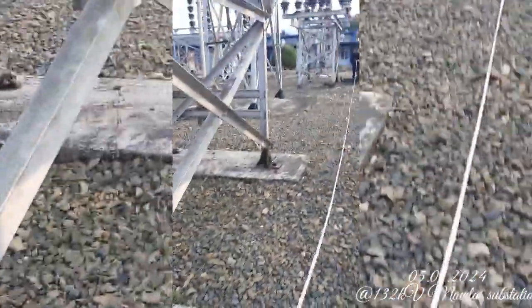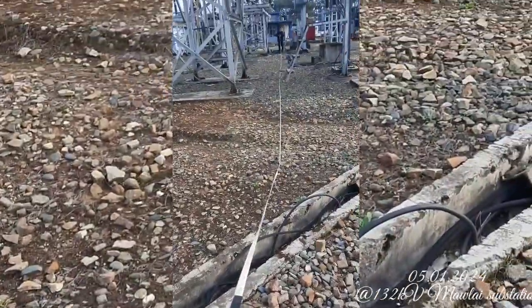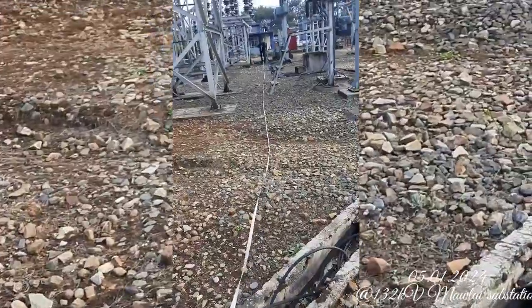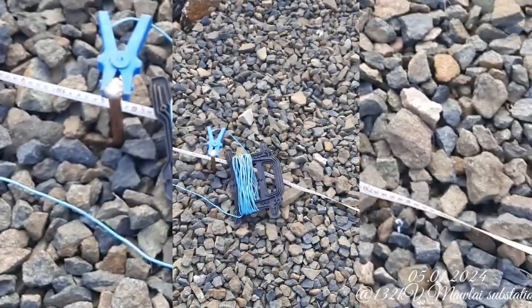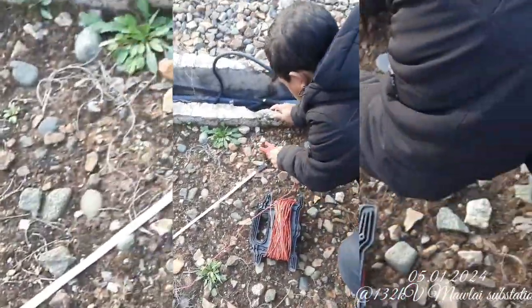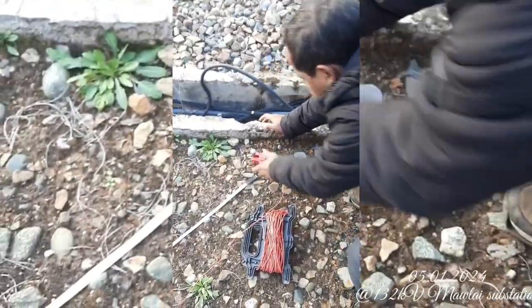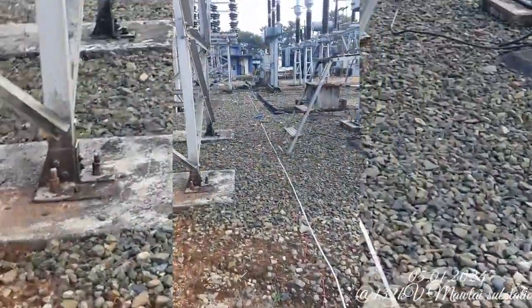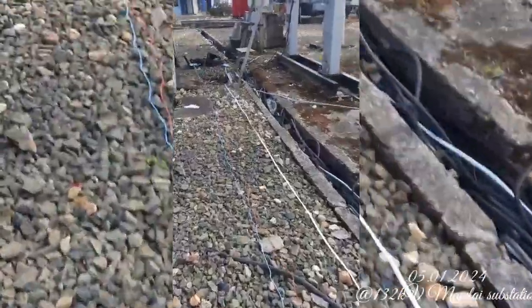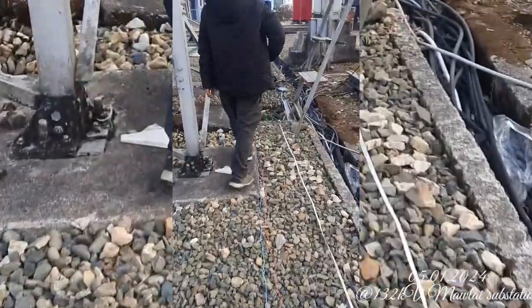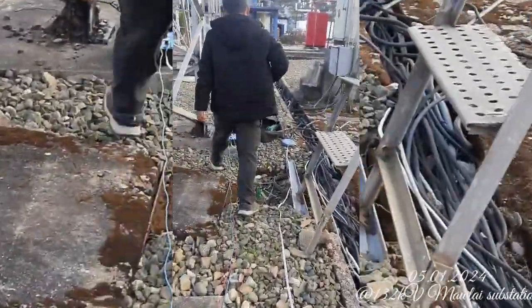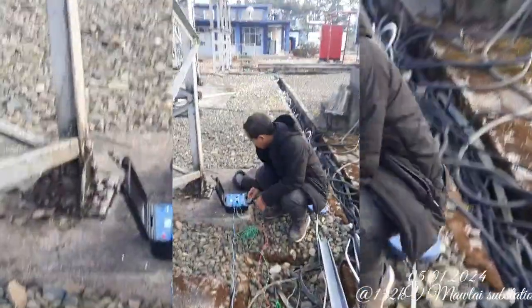In this test, we are going to measure the earth resistance of this 132 kV substation by keeping our voltage electrode at a distance of 10 meters from the earthing pit, the blue one, and keeping our current electrode at a distance of 20 meters, twice the voltage electrode distance, from the earthing pit. Then let's go and see the measurement reading of the resistance.